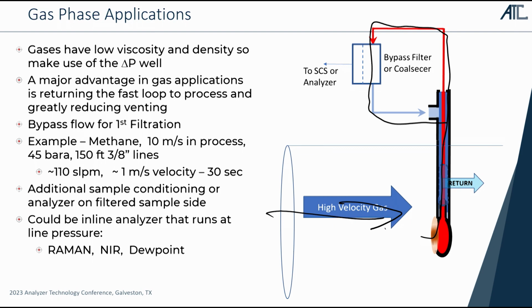And all of the flow gets returned to the process, even if it's at high pressure. So if we have a stream that has, say, H2S in it or methane we don't want to release, it lets us return back at pressure. In a typical example, if I've got about 10 meters per second of flow, which is a typical natural gas pipeline, and I put in 150 feet of 3/8-inch tubing to run my fast loop over, and I'm at 45 bar in that pipeline, typical natural gas pipeline, 600, 650 pounds, I'll drive through that loop at about 1 meter a second. So I get 30-second response time.